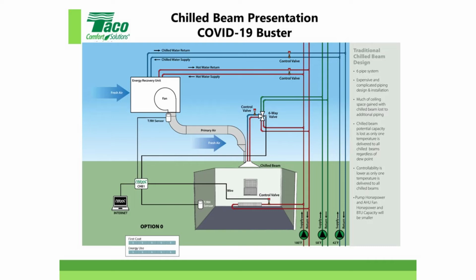Okay? So if you look here, I see 2 red pipes, 2 green pipes, 2 blue pipes. 6 pipes. So you have a supply and return for heating, right? To get to the chilled beam. So start thinking about cost. You have supply and return for heating.